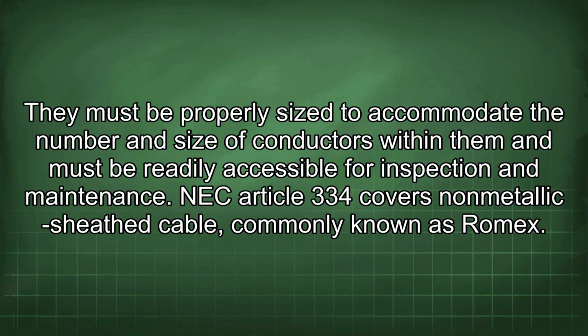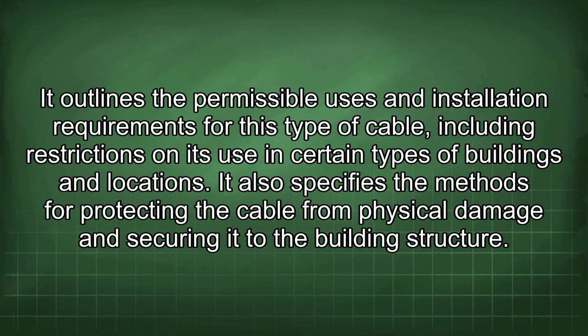NEC Article 334 covers non-metallic sheath cable, commonly known as Romex. It outlines the permissible uses and installation requirements for this type of cable, including restrictions on its use in certain types of buildings and locations. It also specifies the methods for protecting the cable from physical damage and securing it to the building structure.